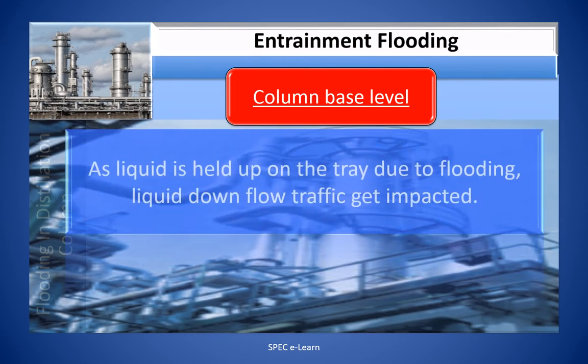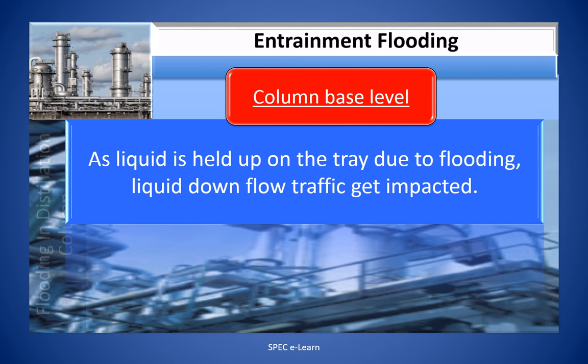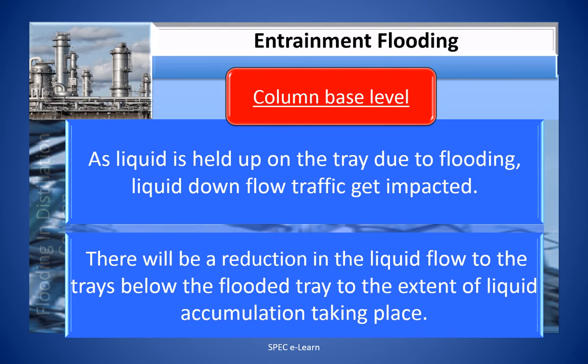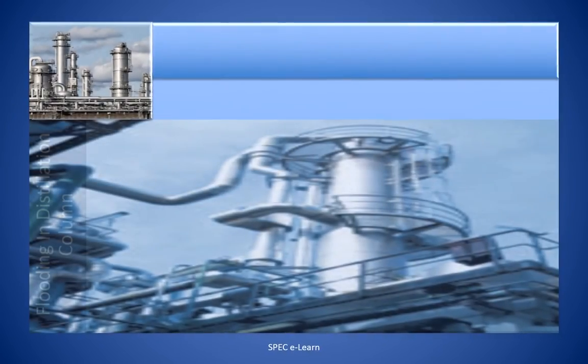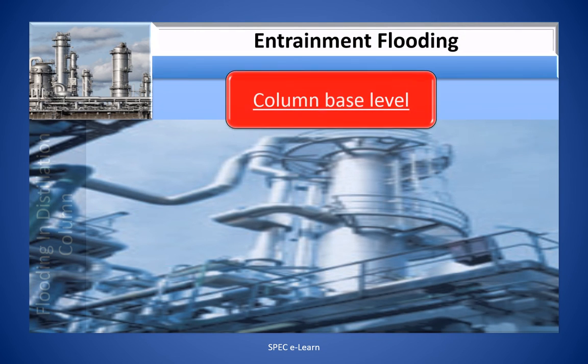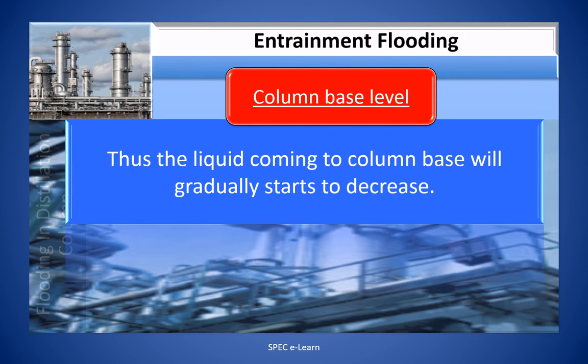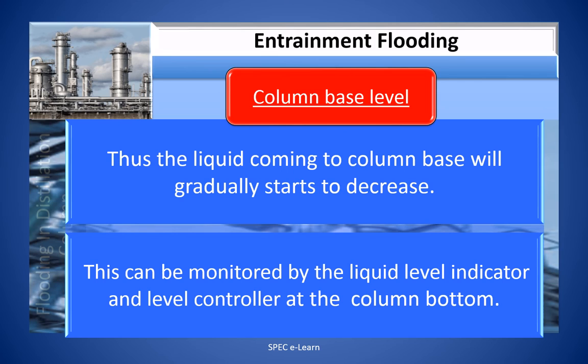As liquid is held up on the tray due to flooding, liquid downflow traffic gets impacted. There will be a reduction in liquid flow to the trays below the flooded tray, to the extent of liquid accumulation taking place. Thus, the liquid coming to the column base will gradually start to decrease, and this can be monitored by the liquid level indicator and level control at the column bottom.